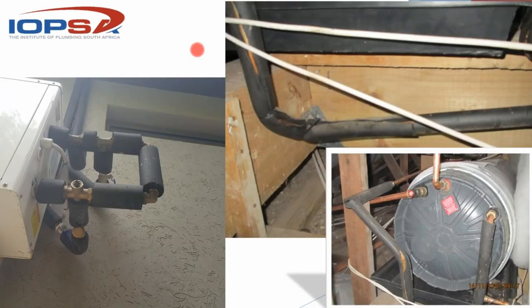Some more don'ts. Again, fittings not covered, not protected. This is not painted, so the heat loss here is almost, you probably shouldn't even have bothered to put any lagging anywhere, because the amount of heat loss here is just ridiculous. Again, it's all fair and well to split a piece of lagging when you have to and put it over a piece of pipe, but then please make sure that you glue it back again and make it sound. Besides that, this piece of lagging is not R1. It's way too thin to be R1. So is this, by the way. I can tell you that at a glance.